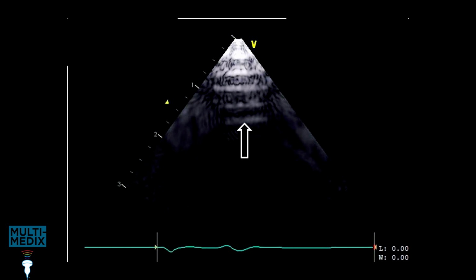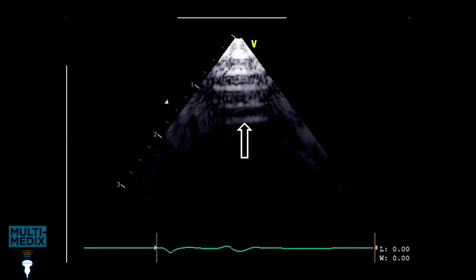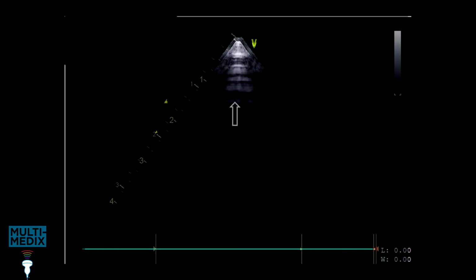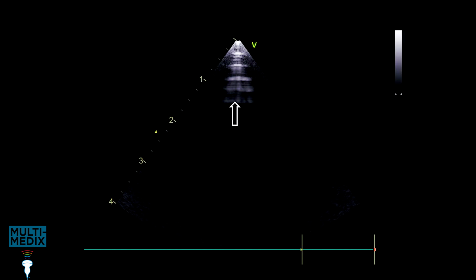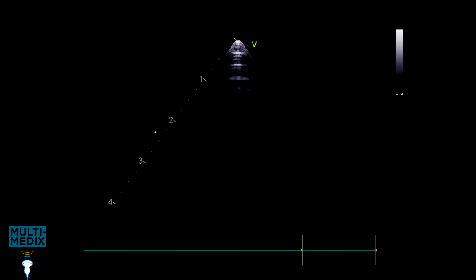Look carefully at the whole deepest reverberation line and turn down the gain until the line completely disappears. Do it again until you've got a consistent result. Compare this result with the baseline tolerance. If any results are out of tolerance, check the scanner settings and repeat the test. Unless the results are grossly out of tolerance, you can still carry on using the equipment, but you need to investigate by doing some sensitivity measurements with a phantom.